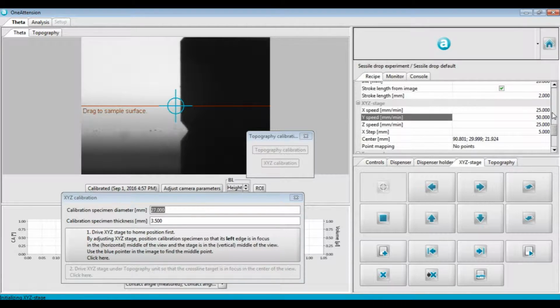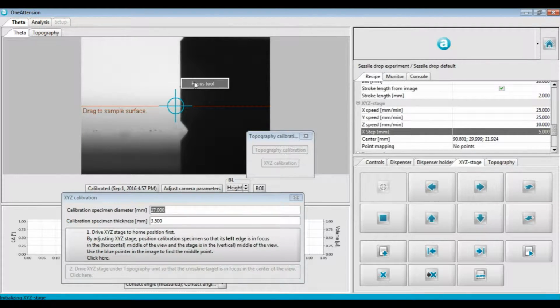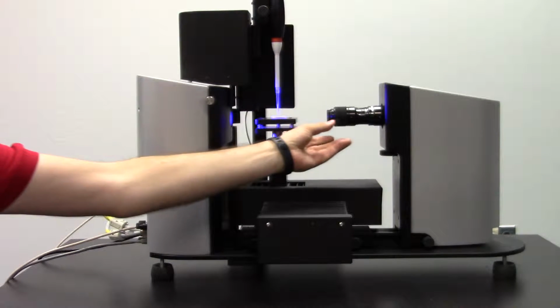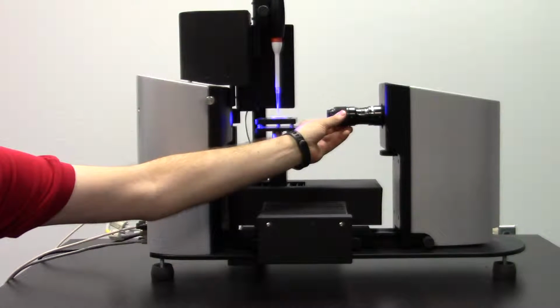Right now I'm in the recipe tab, and I'm decreasing the speeds for the XYZ stage so that I can get more precise movement. Now we need to bring the left edge of the sample into focus, so we can right-click the left edge of the sample to bring up the focus tool. Again, we want to adjust the fine focus until we can maximize the blue peak.